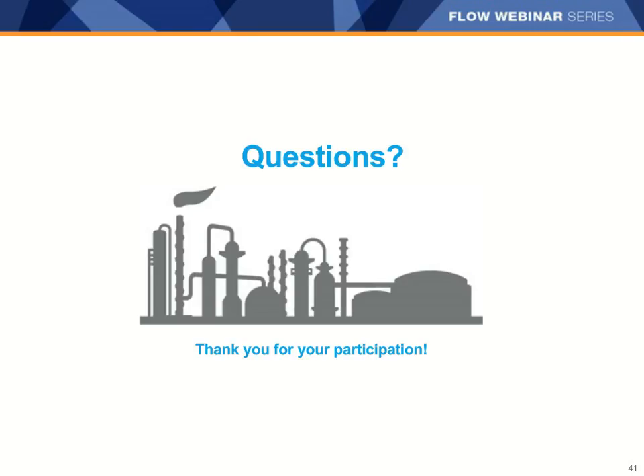So we've got a few questions already on the maximum gas volume fraction that can be handled with these applications. That's a great question, and I'd like to address it by stepping back for a second. There is no maximum gas void fraction limit to, for example, TVR or PVR, because they operate through basically interpolation through events. What's most important for these applications is that these events be intermittent. If you have continuous gas flow, even at, say, 3% GVF, these applications won't do you a lot of good.